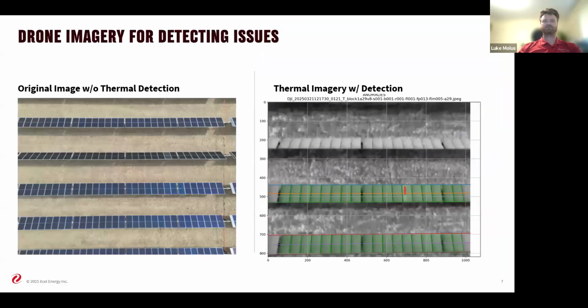So here's a snippet of some of the flights that we've done already. Your original image is on the left without the thermal detection. You can't tell there's anything going on or wrong with the panels here. But if you look on your right, the AI scan and imagery is able to detect each individual panel as seen out in the field. And then it'll tell you, based on temperature differentials and coefficients, whether or not you have an issue going on with one of your panels.